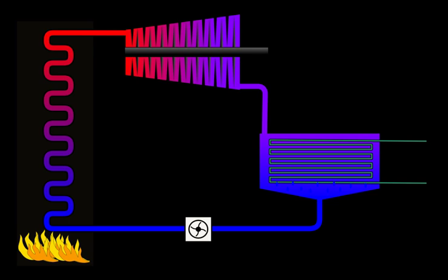This low steam turbine entry temperature is why the Rankine cycle is often used as a bottoming cycle to recover otherwise rejected heat in combined cycle gas turbine power stations. The cold source used in these power plants are usually cooling towers and a large water body. The efficiency of the Rankine cycle is limited on the cold side by the lower practical temperature of the working fluid.